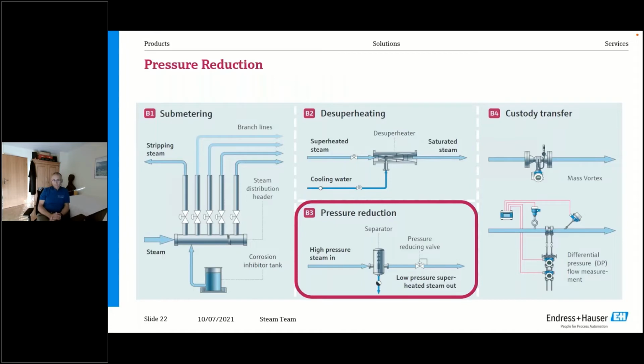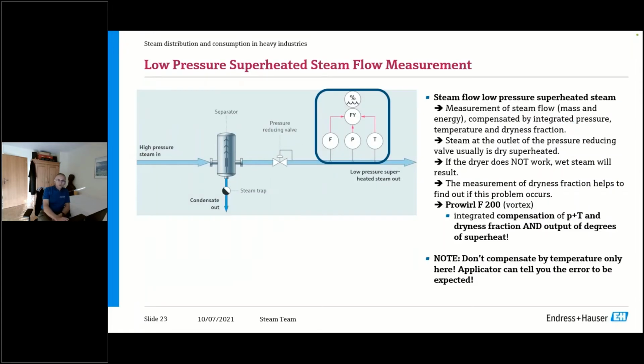Now we're talking about pressure reduction. Especially if you have, for instance, steam coming from a 20 bar grid, and you need, however, steam at 3 bar. What do you do? You reduce the pressure. The desuperheater reduces temperature mainly; pressure reduction reduces pressure. So typically you first send the steam through a separator that takes moisture out, condensing moisture. You have a steam trap located here, and then you send that steam through the pressure reducing valve. Downstream of such a combination, you will always expect superheated steam.